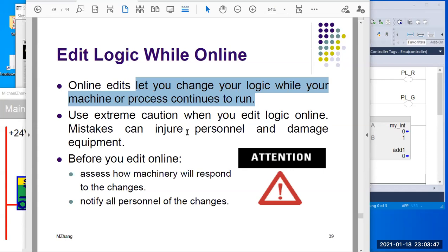Then if you use the offline edit, make changes, do whatever is necessary, when you re-download, your PLC is going to start fresh, from the beginning. But your process has already been completed by 2 steps. In some situations, this is not doable. It's not feasible. You cannot restart the process from the beginning. That is what I mean. So perhaps the online edit is your only choice.